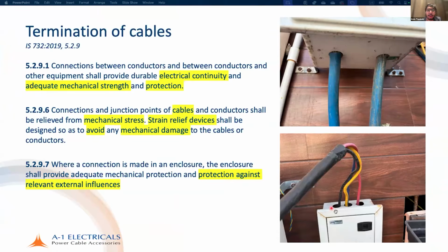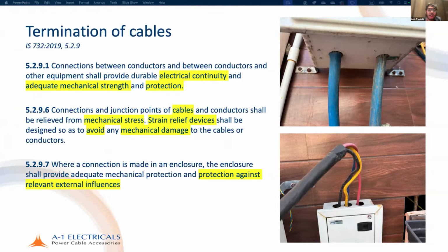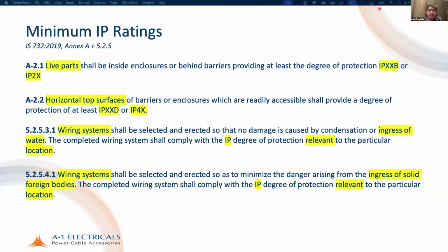If we look at this particular one, this is even worse. We just have holes, and we have conductors entering through these holes. So no ingress protection, no strain relief, no continuity on the armor, absolutely nothing. These are complete violations of the standard, and as we know, these are punishable. When we talk about IP ratings, that's very important.